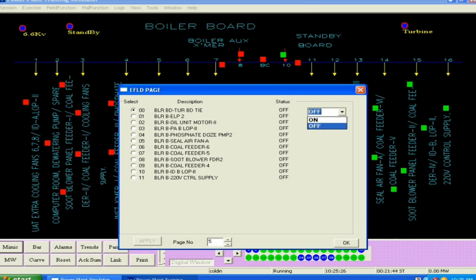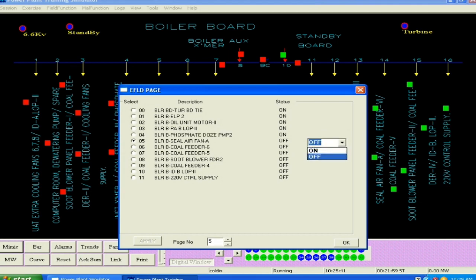And from 1 to 11, index number 11, all the breakers are to be made on, all the supplies are to be extended. So the charging of the boiler board will be complete once you charge all the breakers. Once you charge all the MCBs, these may be MCBs or maybe some breakers, the supply will be extended to these breakers.